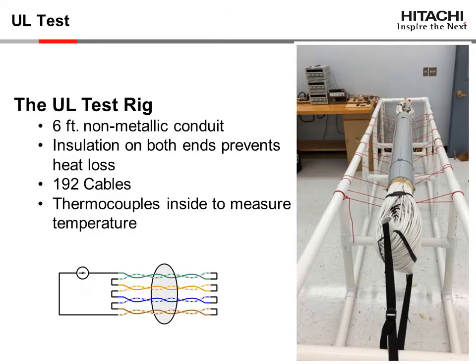How does UL test a cable for LP designation? The test rig, as seen in the picture to the right, is a 6-foot non-metallic conduit with 192 cables placed within. The conduit has insulation on both ends to prevent heat loss, and there are thermocouples placed inside the bundle to record temperature.